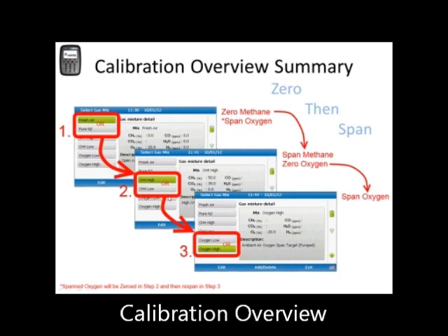Before we begin the calibration process, here's a quick snapshot of the calibration overview summary, which will be explained in detail in the next few steps. Let's go over the main 3 steps to cover the complete calibration, starting with step number 1. As you can see, we give the user 2 options to zero: fresh air and pure N2.